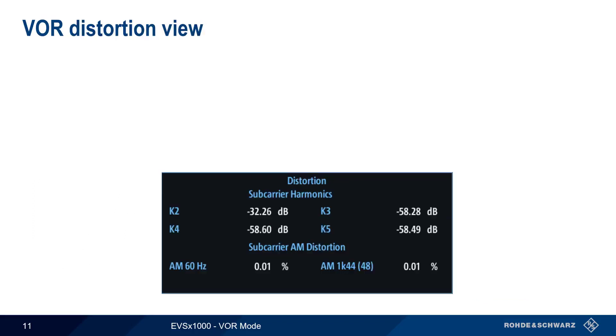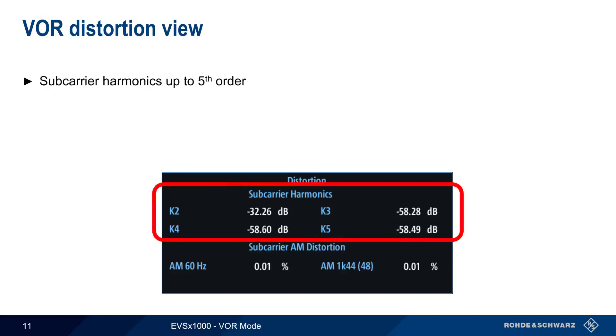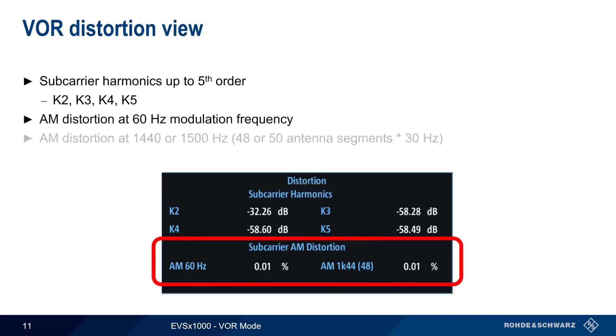In the VOR distortion view, the levels of the 2nd through 5th subcarrier harmonics are displayed. These are indicated as K2 through K5, with values given in dB. Distortion measurement results also include subcarrier AM distortion for 60 Hz and distortion at either 1440 or 1500 Hz, depending on the number of antenna segments.